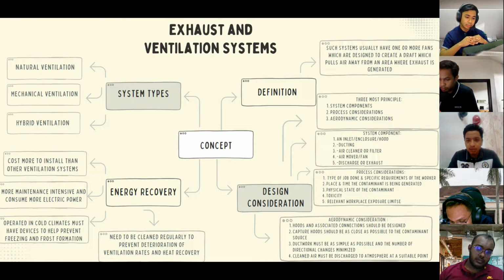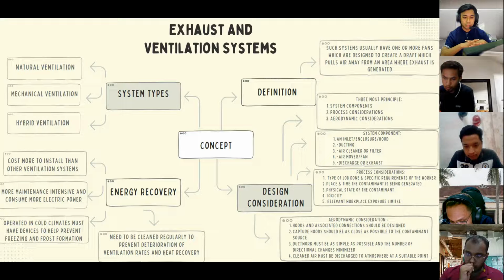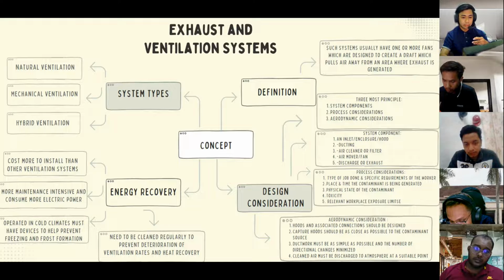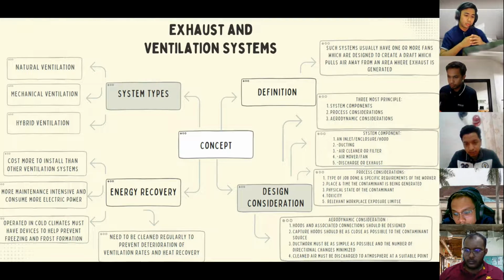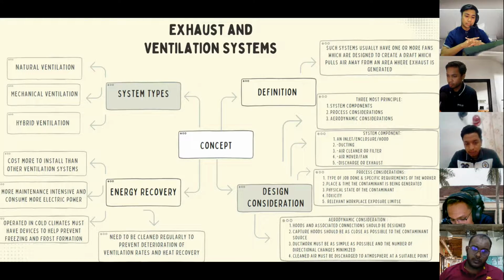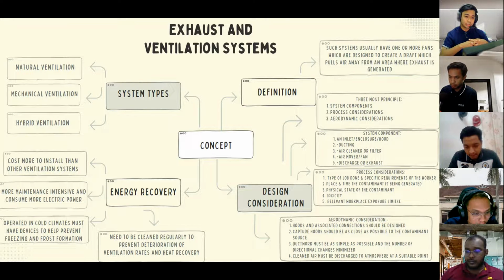There are two types of energy recovery system. The first one is the heat recovery ventilator, HRV, and the energy recovery ventilator, ERV. These both types include a heat exchanger, one or more fans to push the air through the machine, and controls. There are also some small wall or indoor mounted models, but the majority are central whole house ventilation systems with their own duct system or shared ductwork. The main difference between a heat recovery and energy recovery ventilation is the way the heat exchanger works.